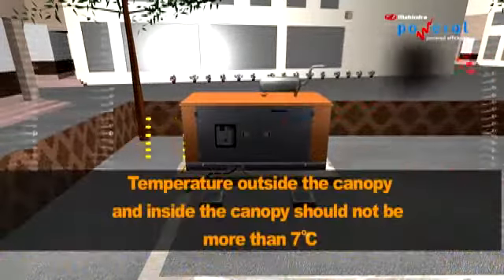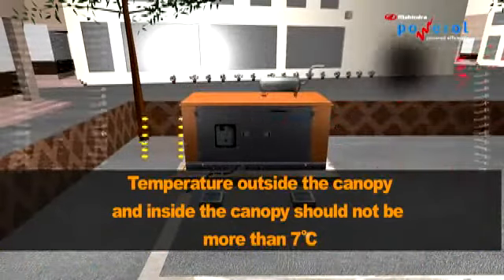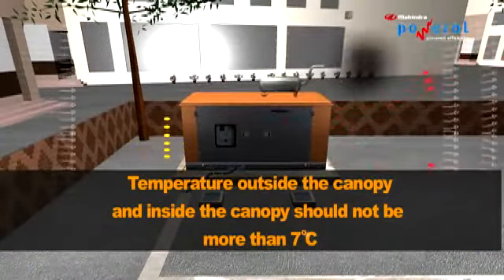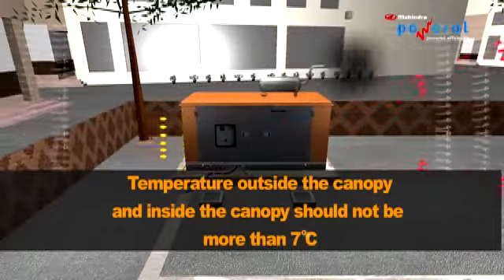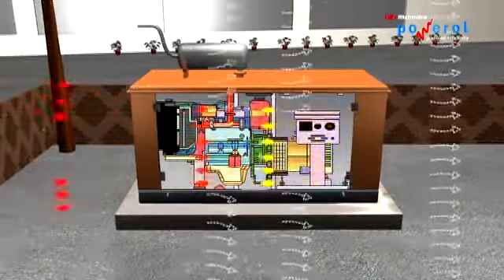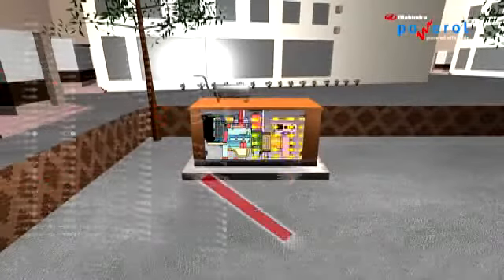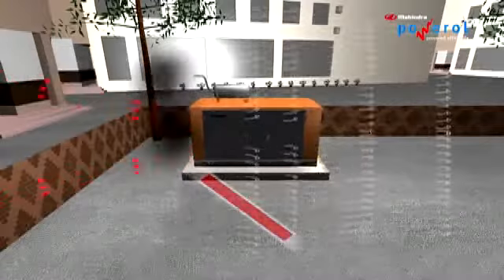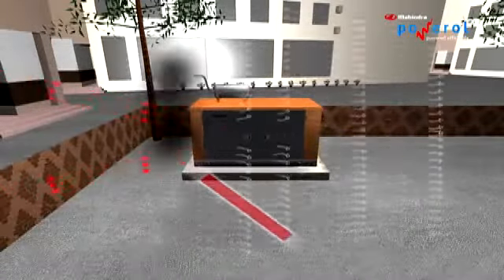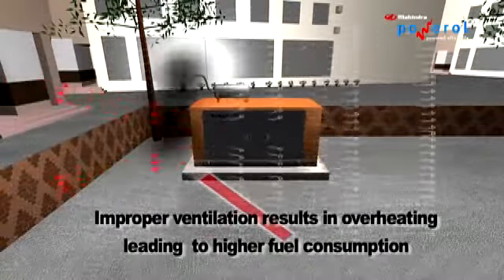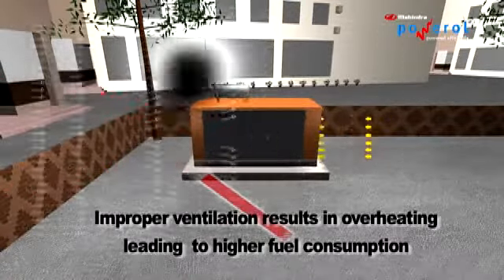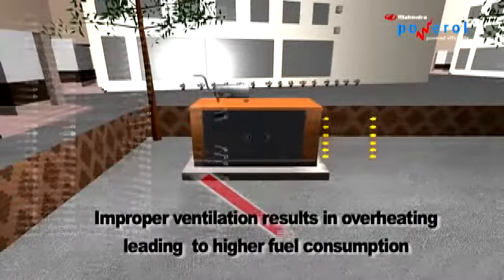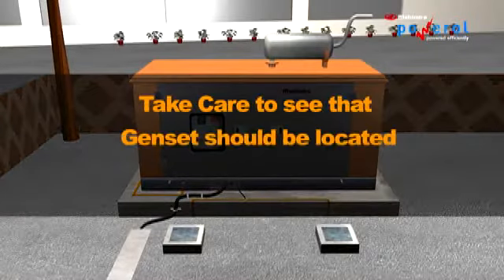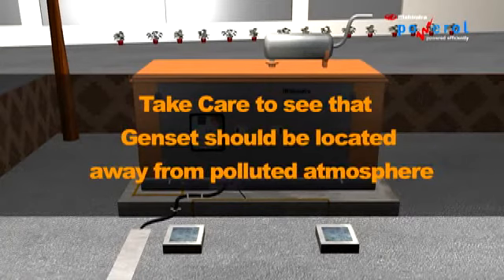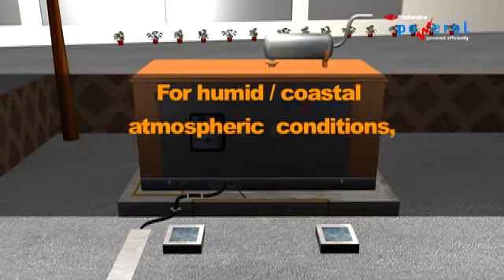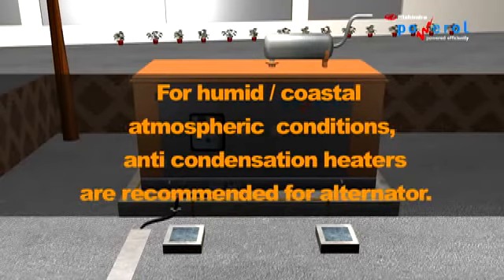The difference between ambient temperature outside the canopy and that inside the canopy should not be more than 7 degrees. The gases must never enter back into the genset or enter into windows, doors or any such other areas. Improper ventilation will result in overheating of the genset, affecting its performance that may lead to higher fuel consumption. Take care to see that genset should be located away from polluted atmosphere. For humid or coastal atmospheric applications, anti-condensation heaters are recommended for alternator.